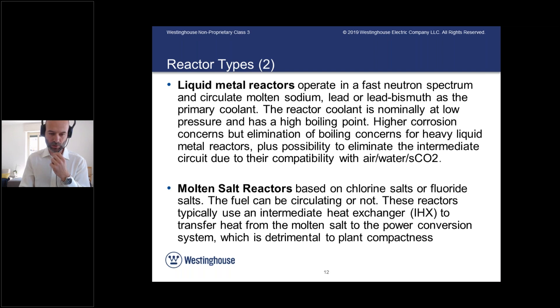Two other reactor types: one is based on liquid metal. If you use liquid metal, you don't have a pressurized system on the primary side — so the benefit is a low-pressure system. It is usually a fast reactor. If the coolant is sodium, then there are lower corrosion concerns compared to lead or lead-bismuth. But there is the concern of boiling and the reaction between sodium, air, water, and supercritical CO2. Whereas with heavy liquid metal, it is possible to eliminate the intermediate circuit and make the reactor more compact, due to lead having benign reactions with air, water, and supercritical CO2.